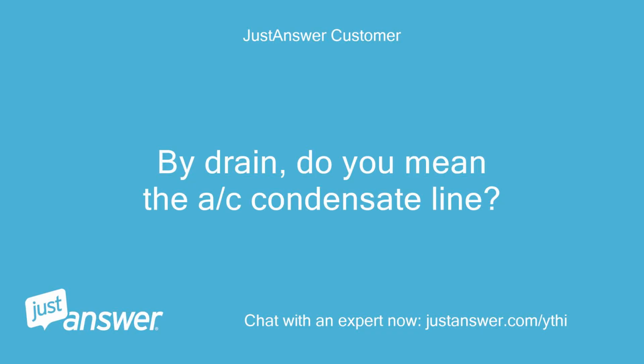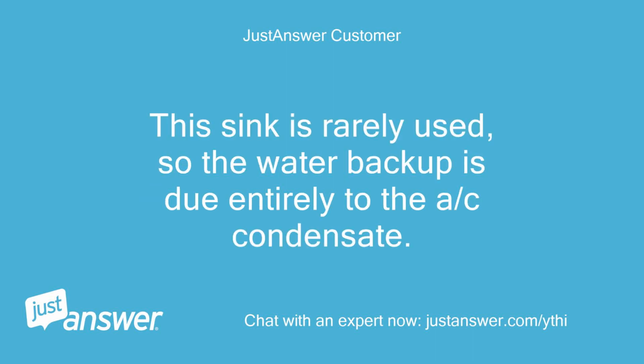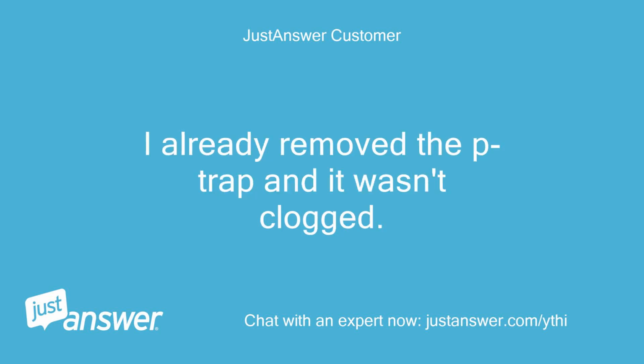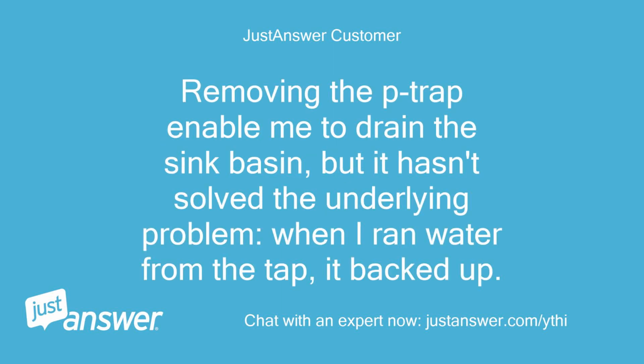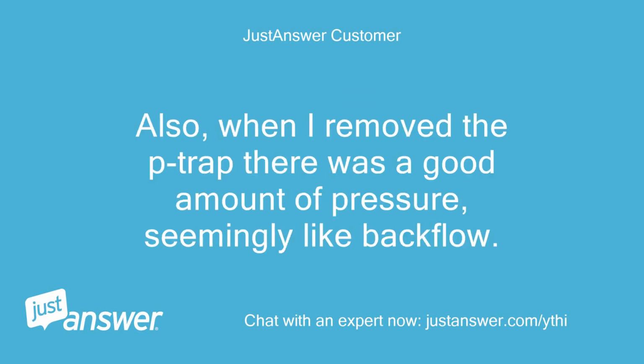By drain, do you mean the AC condensate line? This sink is rarely used, so the water backup is due entirely to the AC condensate. I already removed the P-trap and it wasn't clogged. Removing the P-trap enabled me to drain the sink basin, but it hasn't solved the underlying problem. When I ran water from the tap, it backed up. Also, when I removed the P-trap, there was a good amount of pressure, seemingly like backflow.